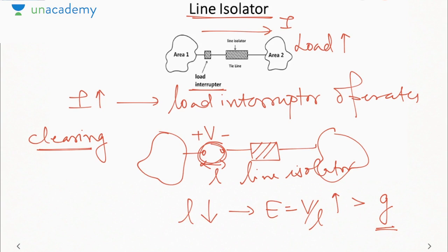So when does it operate? After the load interrupter operates. And after the load interrupter operates, what will be the current in the system? It will be 0. So that means the line isolator will operate at a 0 current, or it operates under no load condition. Okay. So far we have seen 3 types of switches: fuse, line isolator and load interrupter. Fuse operates under abnormal condition, then load interrupter operates at full load condition, then line isolator operates at no load condition.